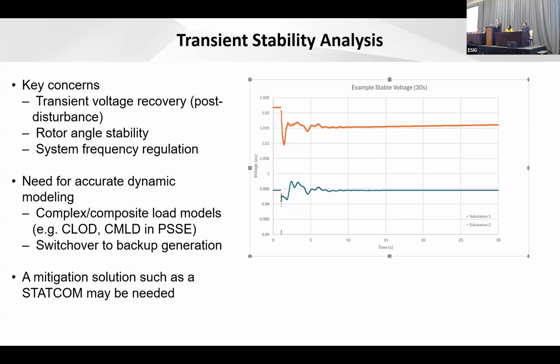But the key is the modeling. You really need to have an accurate dynamic model of these data centers—you just can't use simplified models like you could with some other loads. I've listed some examples here: if you're using PSS/E, you need to use composite complex load models. That's why you need to know how much percentage is IT load, how much percentage is motor load, because you need to model these individually.